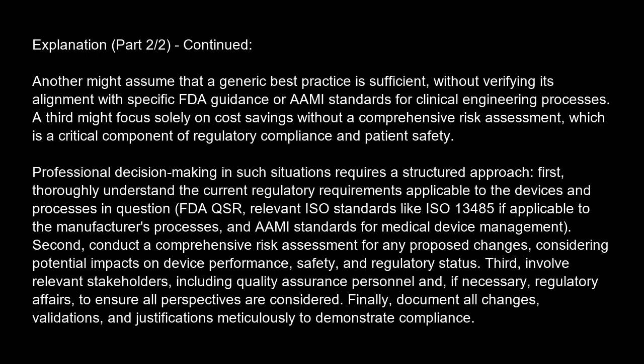Professional decision-making in such situations requires a structured approach. First, thoroughly understand the current regulatory requirements applicable to the devices and processes in question: FDA QSR, relevant ISO standards like ISO 13485, if applicable to the manufacturer's processes, and AAMI standards for medical device management.